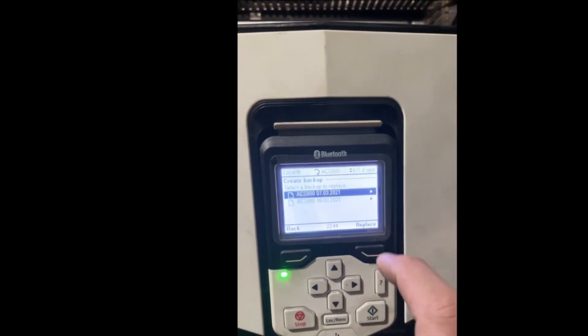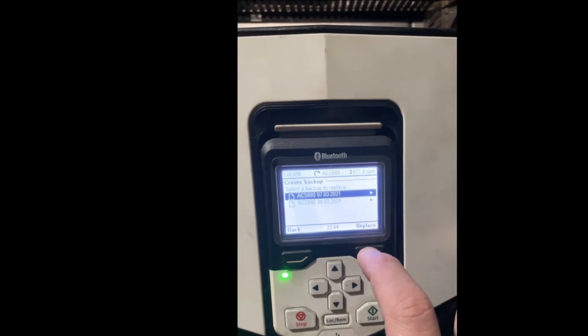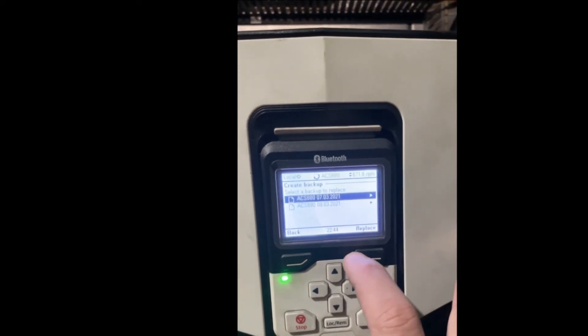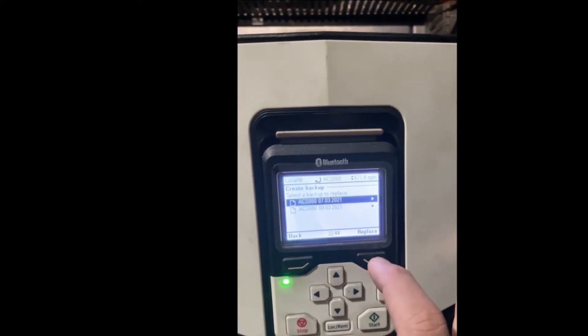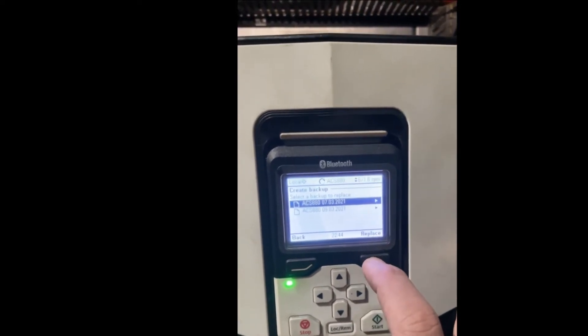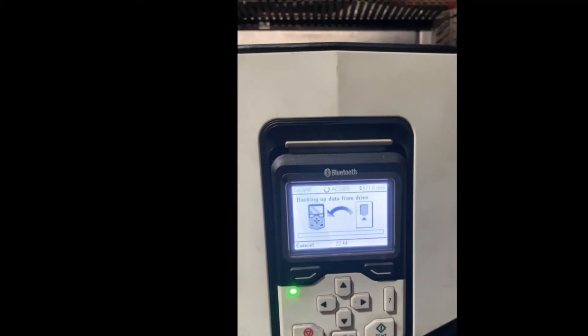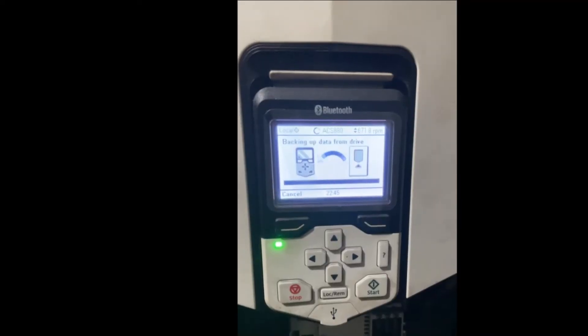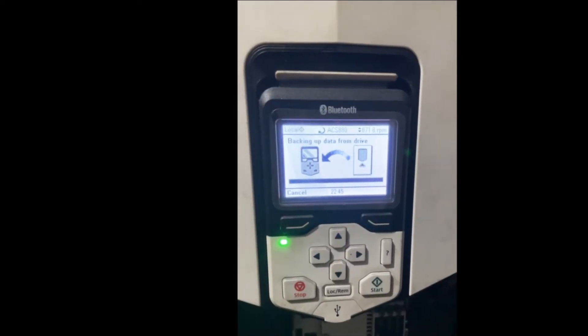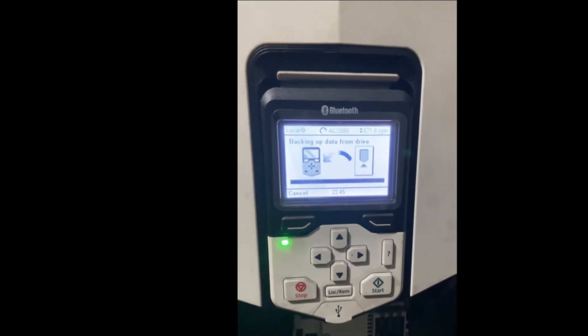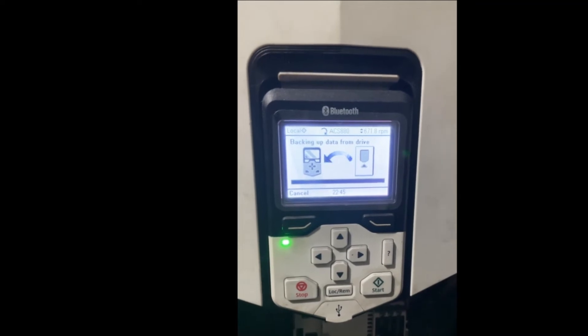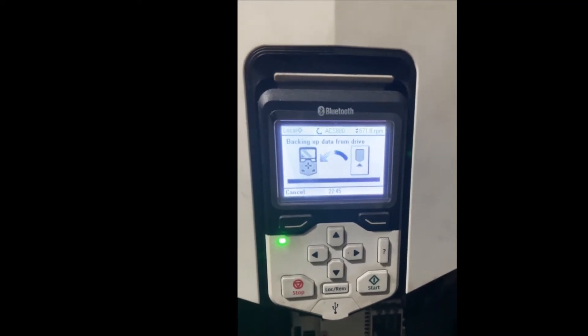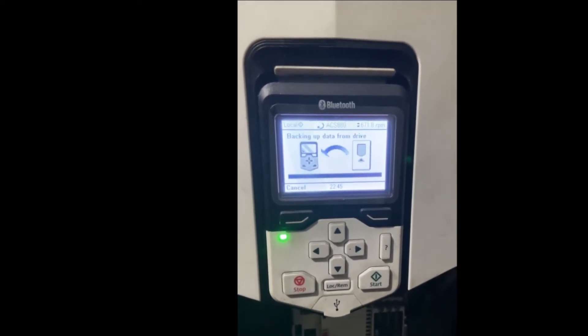For now we're going to create a backup, so we press Select. Here it asks us which backup you want to replace from the old ones. We're going to replace the older date, so I'm going to press Replace. Now we will wait until it finishes backing up — copying the parameters from the drive to the panel.